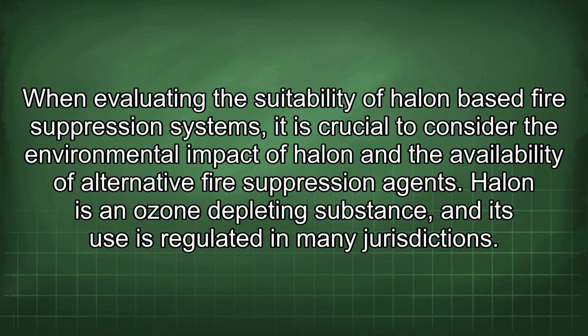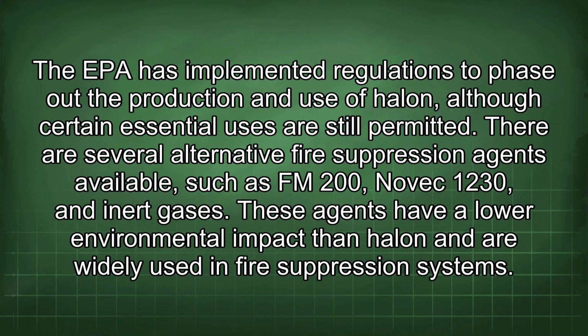When evaluating the suitability of Halon-based fire suppression systems, it is crucial to consider the environmental impact of Halon and the availability of alternative fire suppression agents. Halon is an ozone-depleting substance, and its use is regulated in many jurisdictions. The EPA has implemented regulations to phase out the production and use of Halon, although certain essential uses are still permitted. There are several alternative fire suppression agents available, such as FM200, Novec 1230, and inert gases. These agents have a lower environmental impact than Halon and are widely used in fire suppression systems.